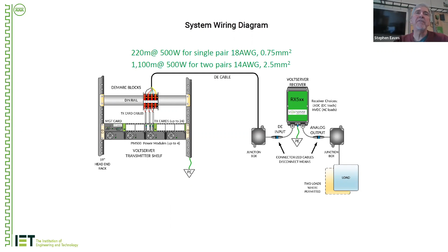I try to give folks an idea of the capabilities here on top. With about 500 watts of transmission, you can go 220 meters on 18 gauge cable and 1100 meters on 14 gauge. To get the full 2000 meter transmission, we usually do that on 12 gauge, and you have to reduce the power levels per pair as you go further in distance. But these 500 watt levels are fairly reflective of what many of the installations are out there.